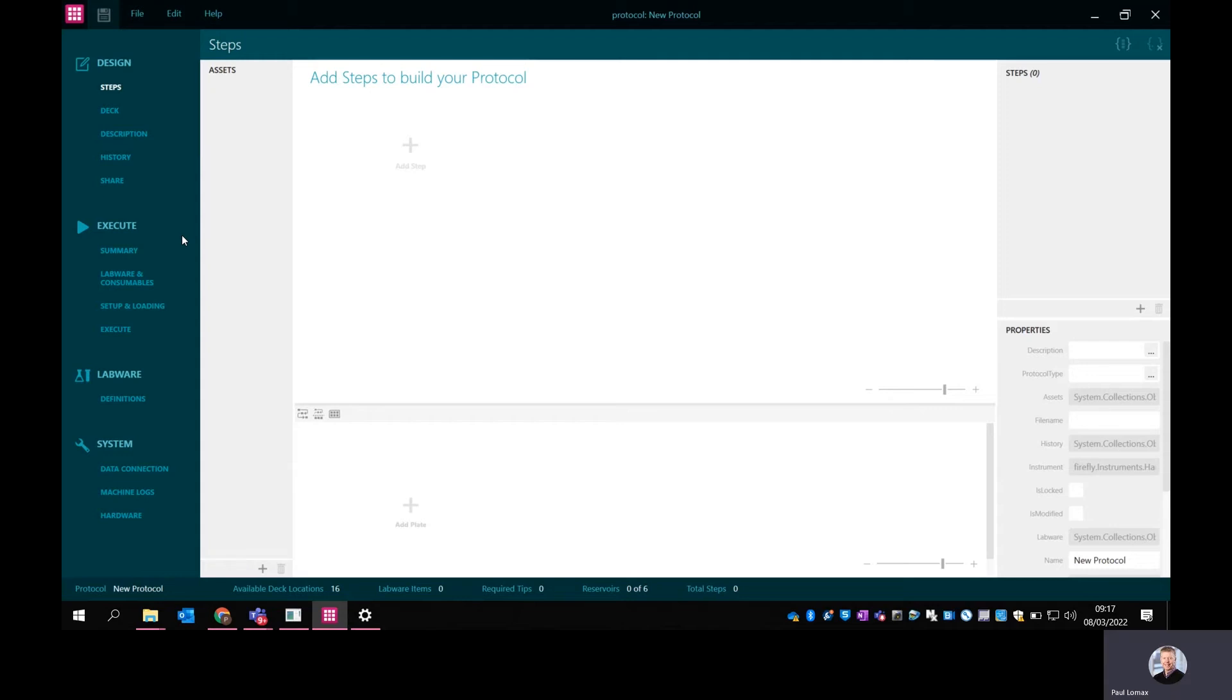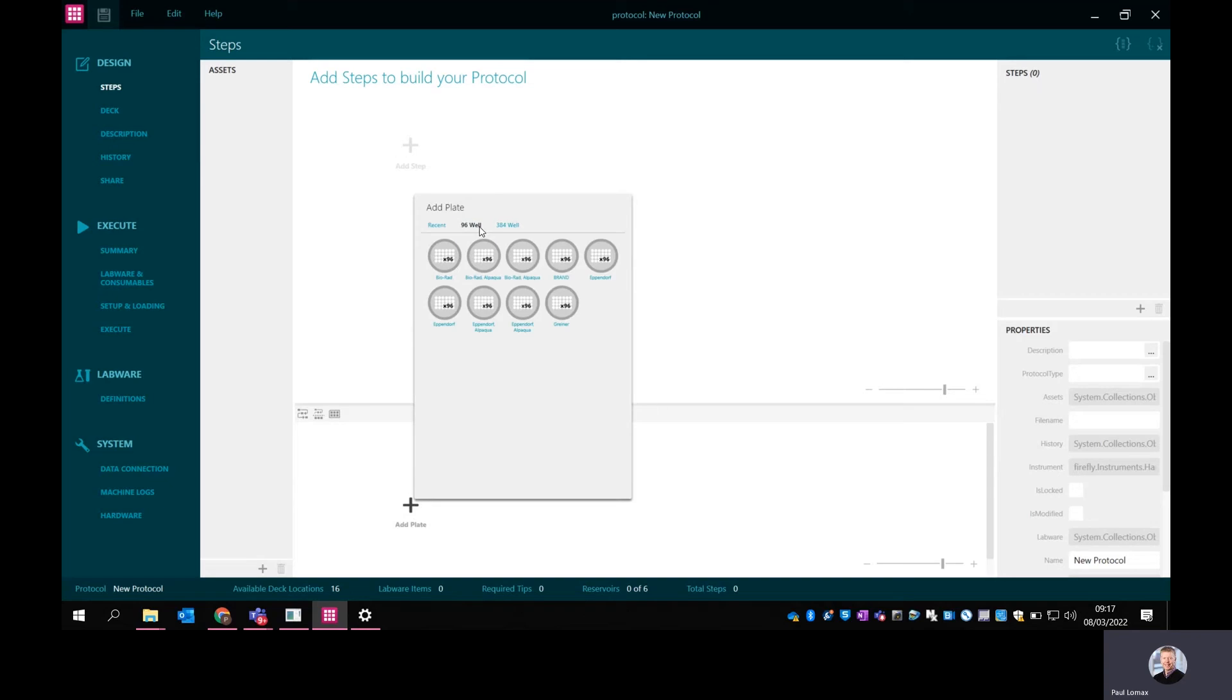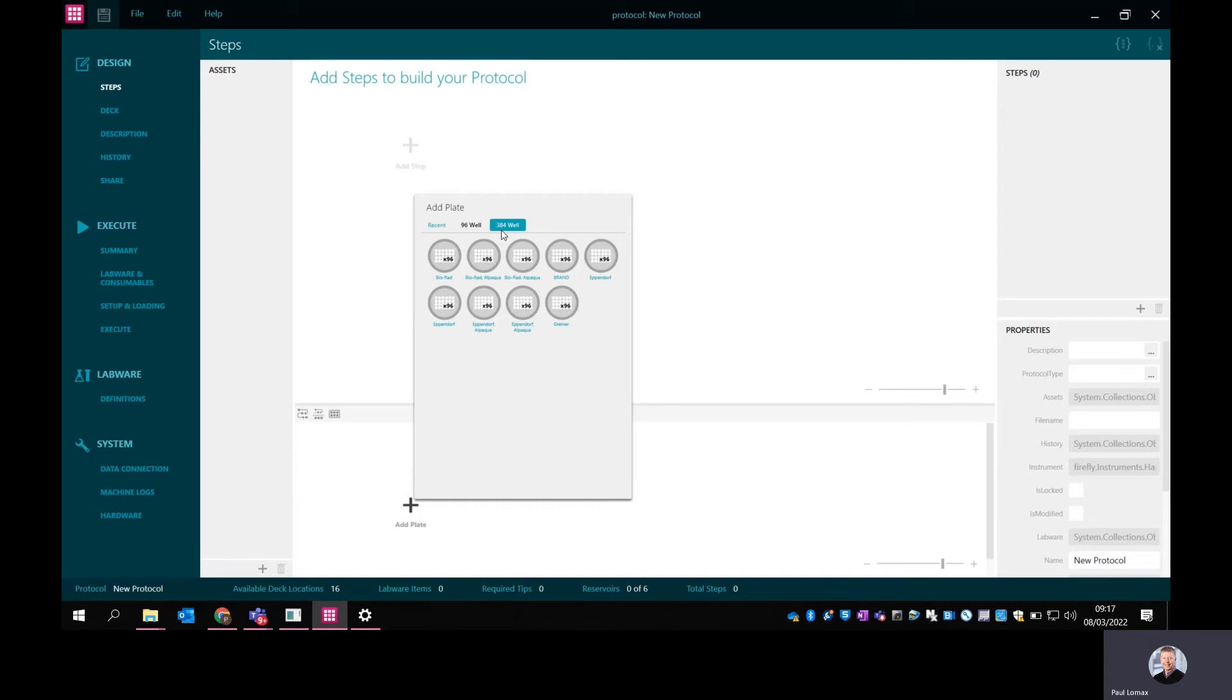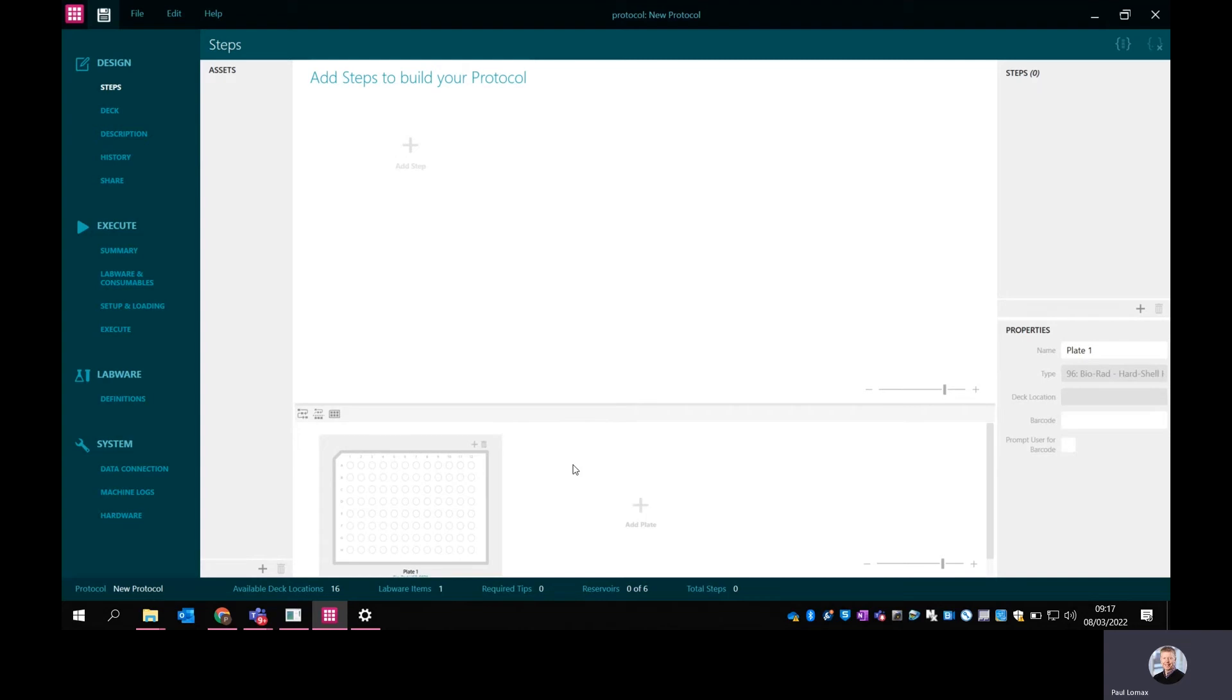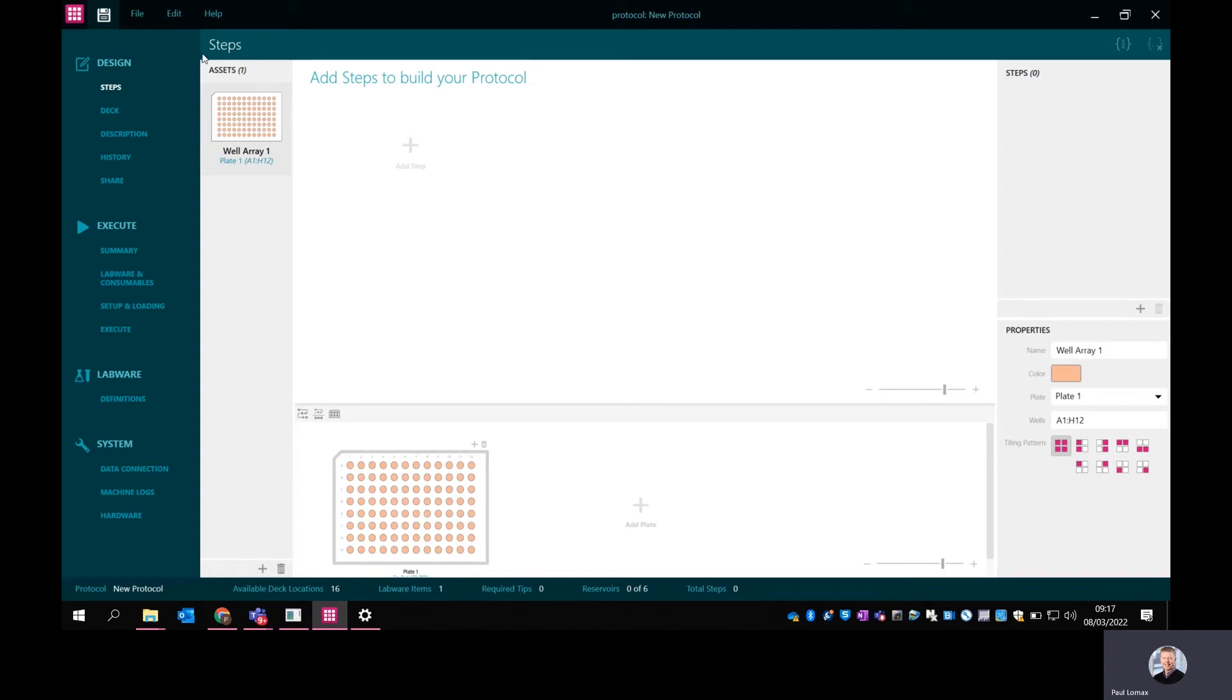I'm going to run through the steps to build a simple protocol. First, I'm going to add a plate. We've got choices of 96 and 384 - these are just the ones I've got loaded here. There's a large library you can download different plate definitions from, and you can build your own plate definitions as well. I'm going to use a 96-well plate, select the whole plate, and add that to the working list called assets. This is essentially the things I'm going to be using. The protocol will build up in this left panel here. I'm also going to name that DNA.